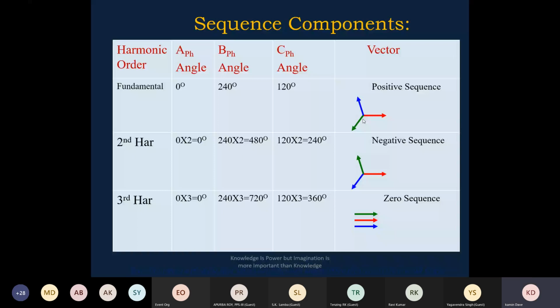When we consider the second harmonic, 0 into 2 is 0, 240 into 2 is 480, and 120 into 2 is 240. So 480 minus 360 is 120 degrees. So it is 0, 120 degrees, 240 degrees. That is, A phase is 0 degrees, B phase is 120 degrees, C phase is 240 degrees, which is called negative sequence. When there is a second harmonic, the negative sequence component will be significantly increased.